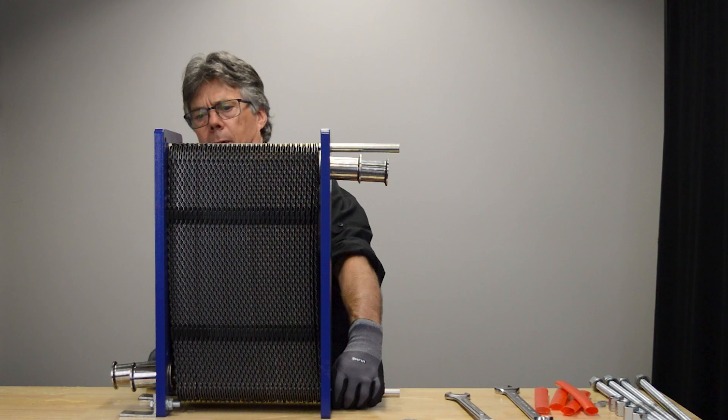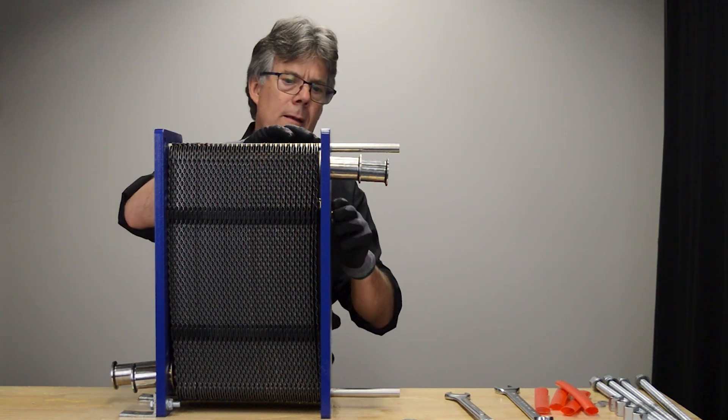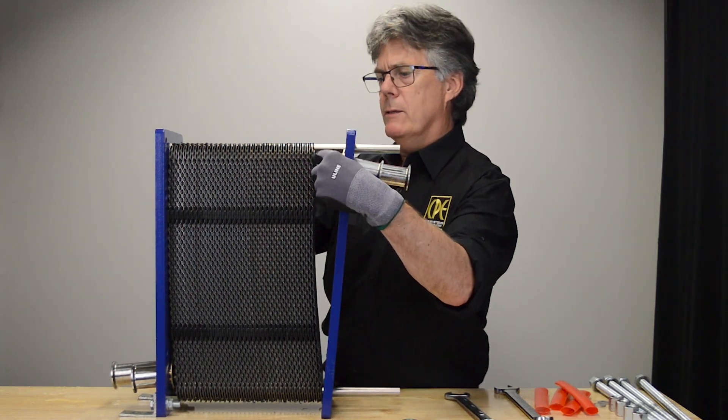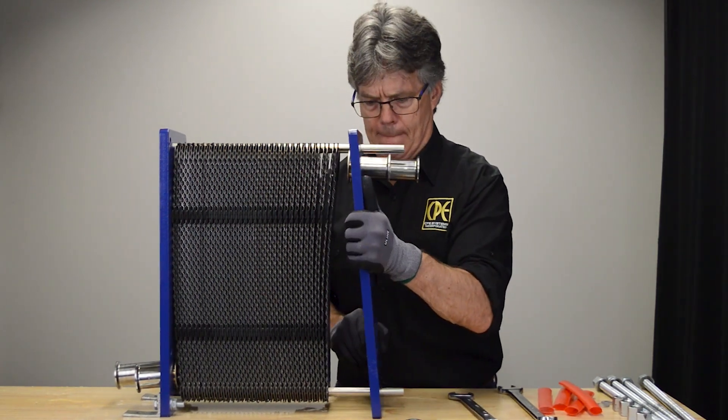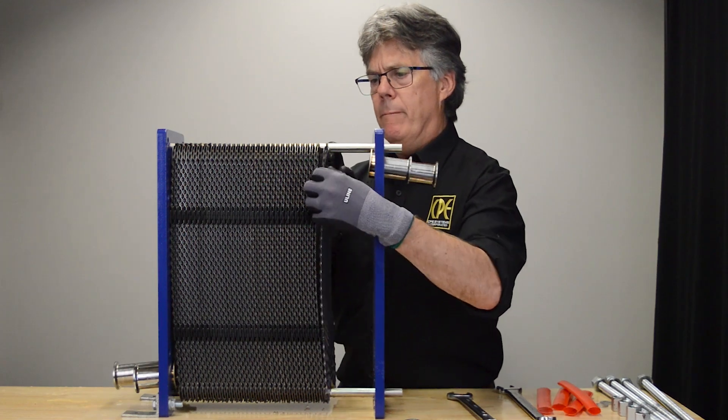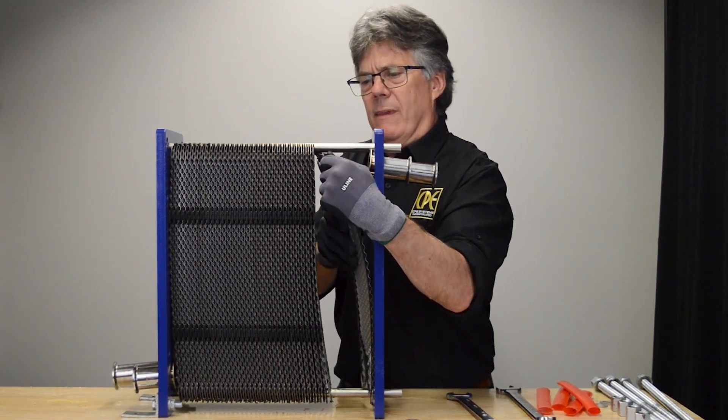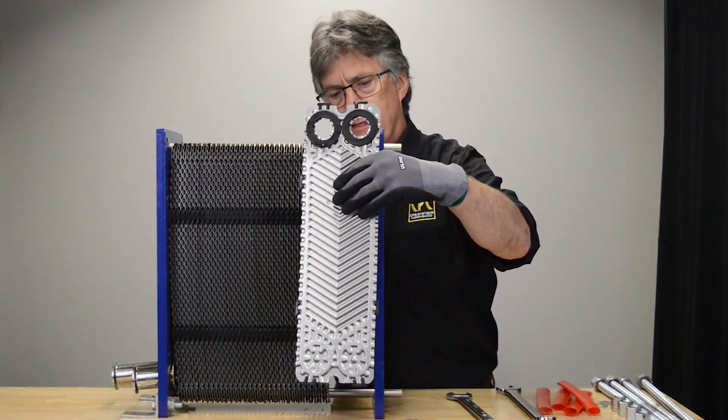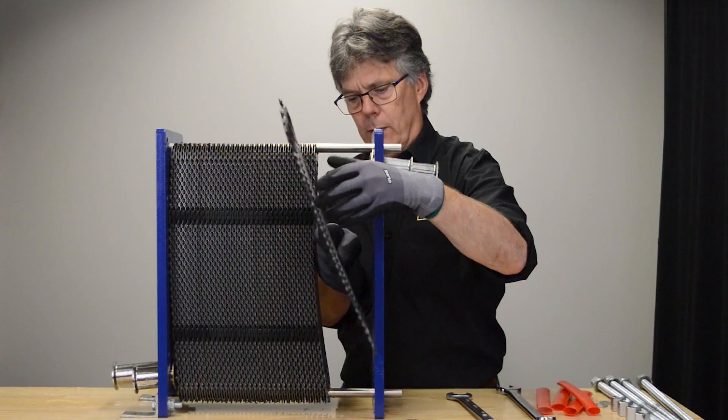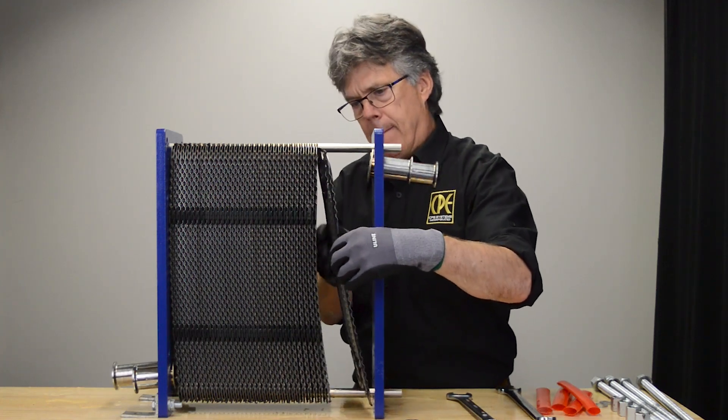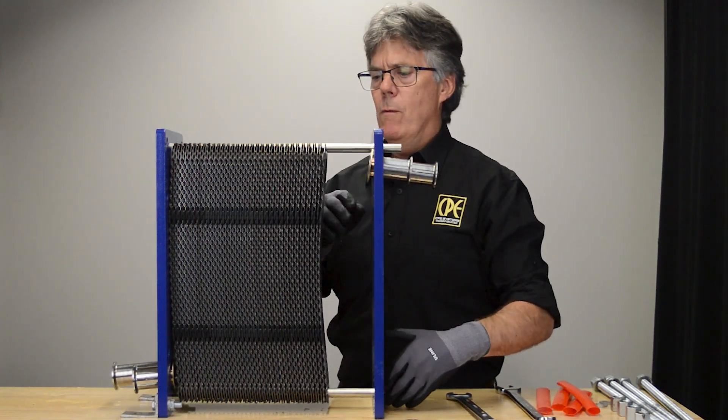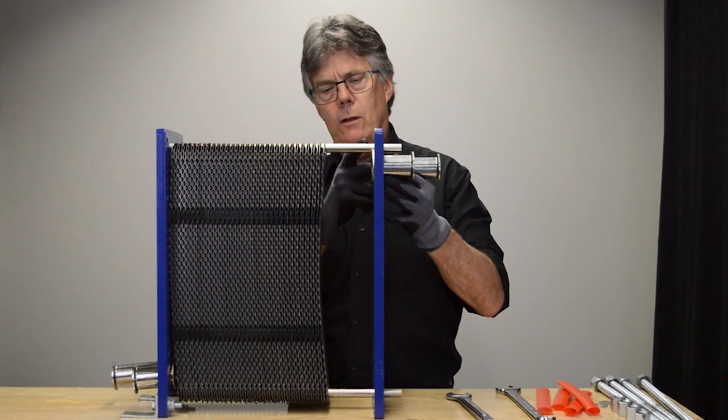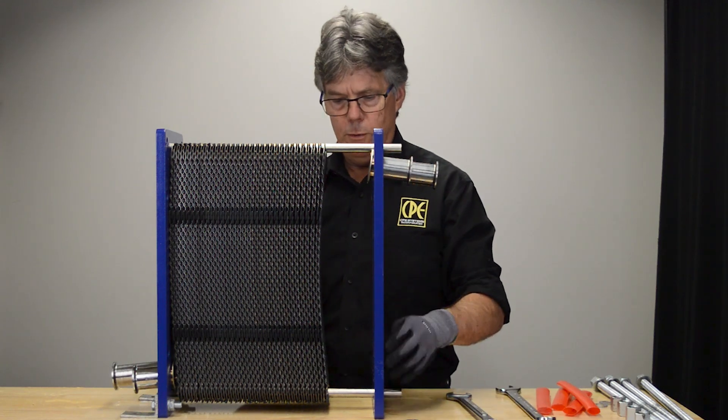Now we've got a honeycomb pattern here. On the other end of the plate, you'll see there's just little ring gaskets on this one. This is the middle one, and this one has a gasket on this side, like all the others. We have ring gaskets on this side to join onto these ports, so it doesn't leak. On the end, only that one has the ring gaskets on it. We have the port connections. You see it's the same all the way through, so no liquid touches the blue part.